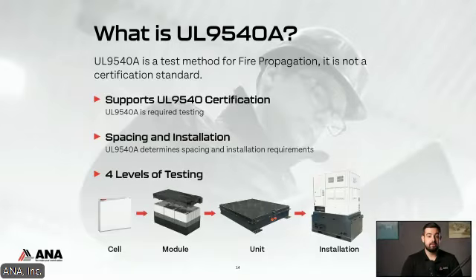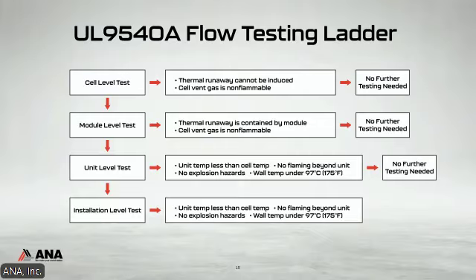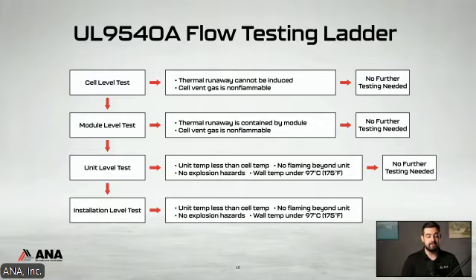Four levels of testing are listed out in this 9540A. So it is cell, module, unit, and install level. And I'm going to touch on these on the next slide. So this slide shows the 9540A flow testing ladder. So this relates back to the four levels of testing that I mentioned previously. You do start with your cell level test. So your certification body, your testing lab is going to do everything they can to induce thermal runaway at your cell level, right? Whether this is a high ambient test, 60, 70 C oven. This could be a piercing test. It could be an overcharge or undercharge test.